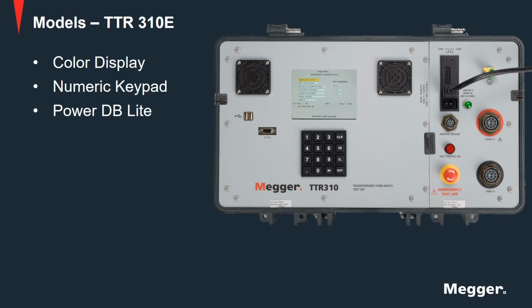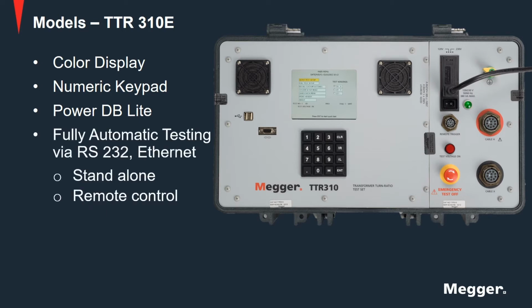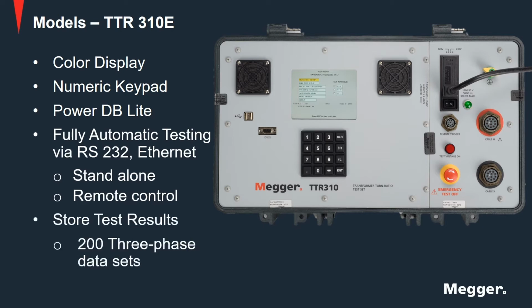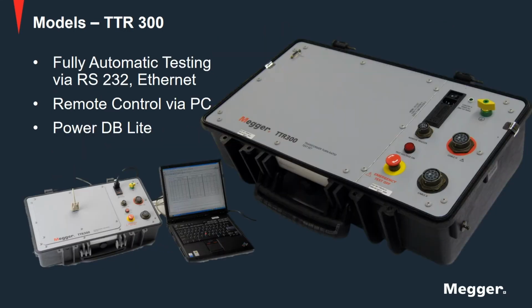First is the TTR310E that has a color display, a numeric keypad, and can use the PowerDB Lite software. It can perform fully automatic testing via RS-232 or the Ethernet interface, and it can perform testing standalone or it can be remote controlled via the PC. It can store results up to 200 three-phase datasets. Second is the TTR300 that allows for fully automatic testing via either RS-232 or Ethernet. It can be remote controlled via an external PC using the PowerDB Lite software.